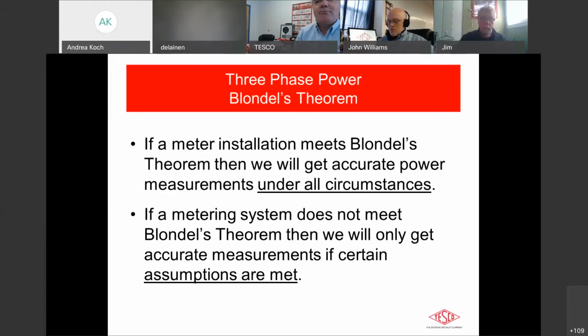Well, we've got a lot of meter forms, which is what we're talking about today. We talked a little bit about that last week. Our basic 2S meter, the meter that we have over 85% of just about all of your distribution systems are probably 2S meters. They're not really the right meter to have out there. That's a 3-wire service, and you have 1 watt meter. Which means the 2S meter does not meet Blondel's theorem. Well, what the heck does that mean? That means that it is not measuring your service very accurately.